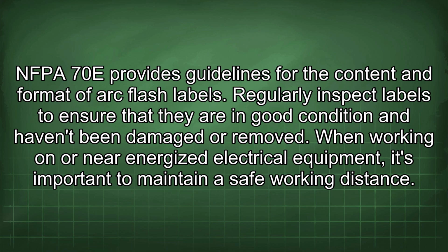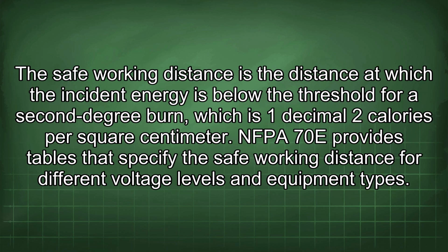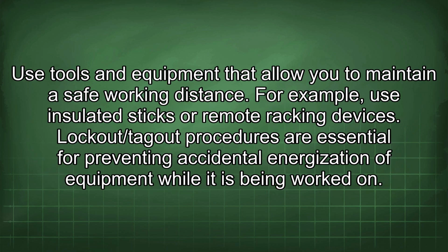When working on or near energized electrical equipment, it's important to maintain a safe working distance. The safe working distance is the distance at which the incident energy is below the threshold for a second-degree burn, which is 1.2 calories per square centimeter. NFPA 70E provides tables that specify the safe working distance for different voltage levels and equipment types. Use tools and equipment that allow you to maintain a safe working distance. For example, use insulated sticks or remote racking devices.